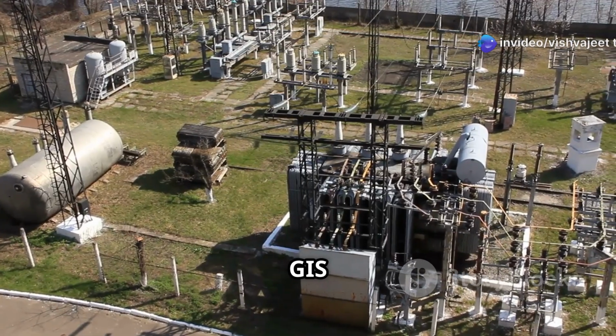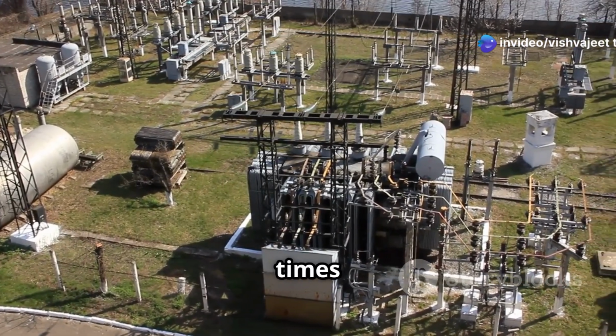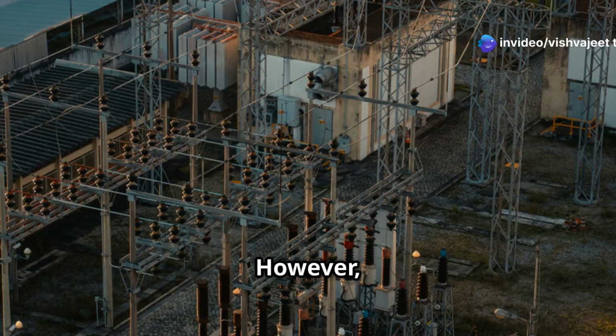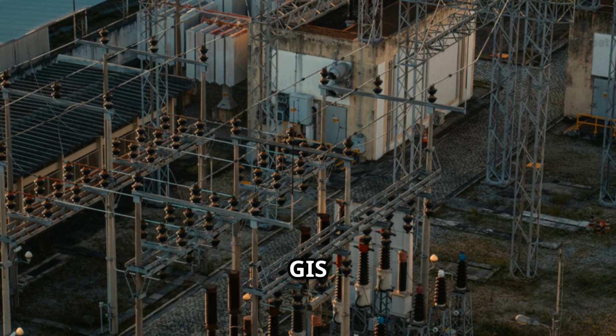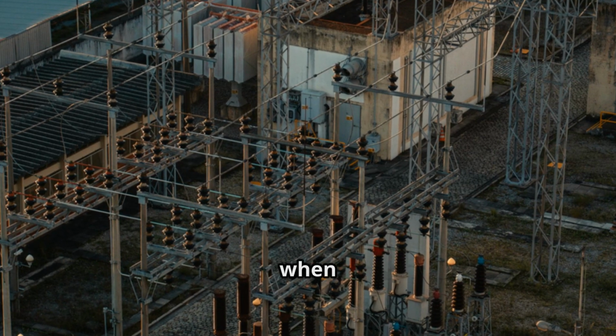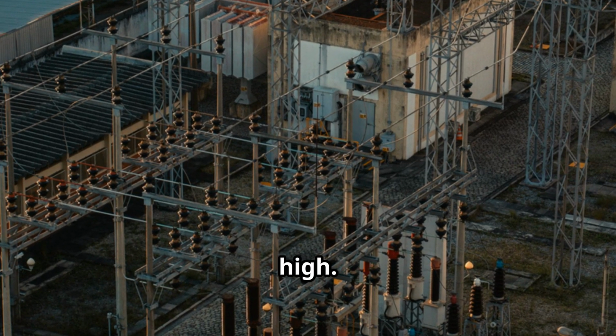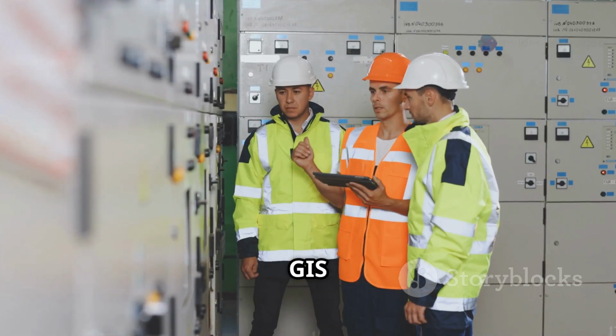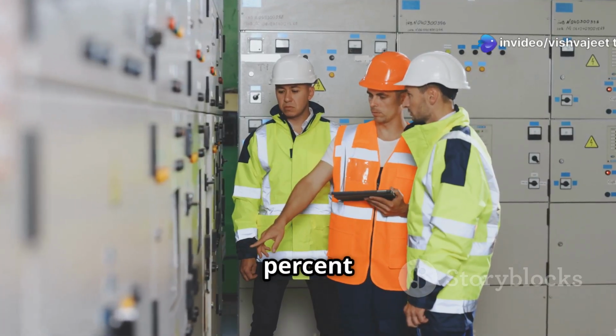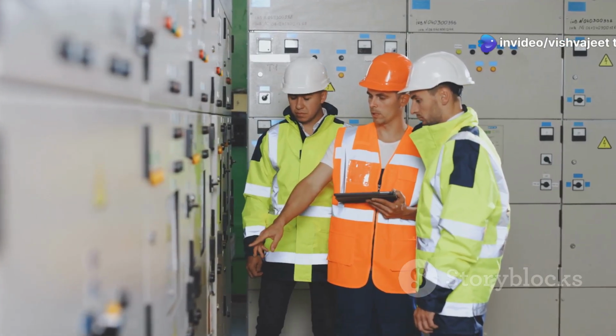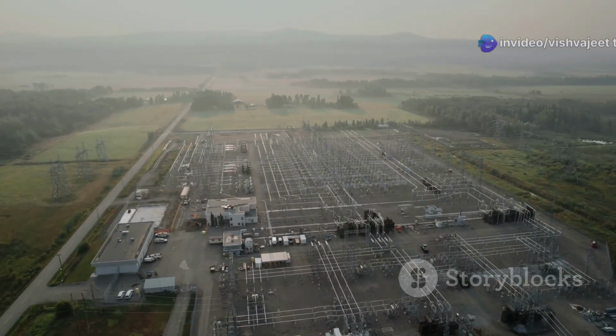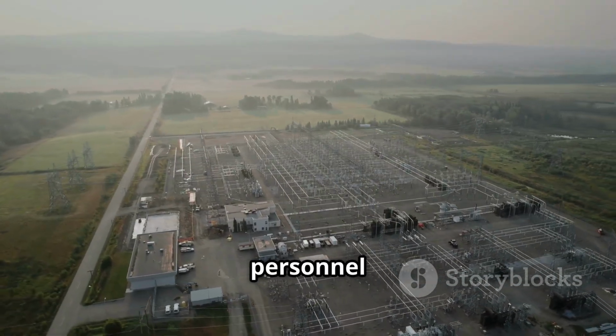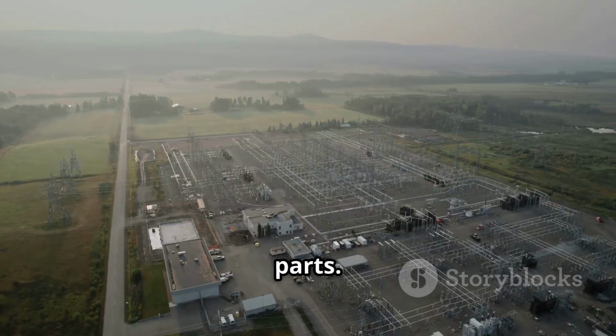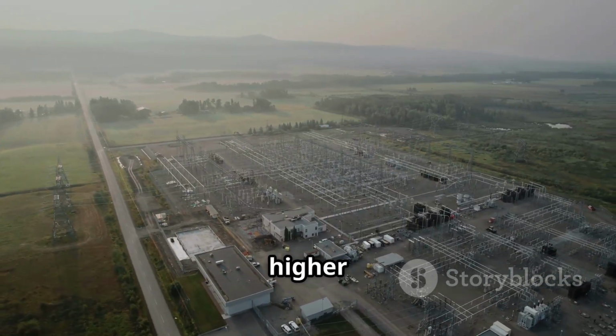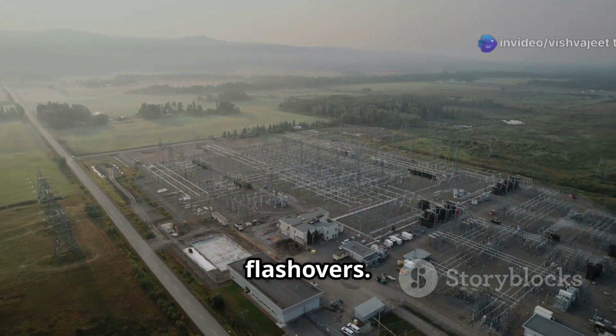The initial cost of GIS is typically 2 to 4 times more expensive than AIS. However, the life cycle cost of GIS is often more economical when land costs are high. On top of that, the maintenance cost of GIS is generally 30 to 50% lower than AIS. GIS provides better personnel safety with enclosed live parts. AIS, on the other hand, has a higher risk of electrical flashovers.